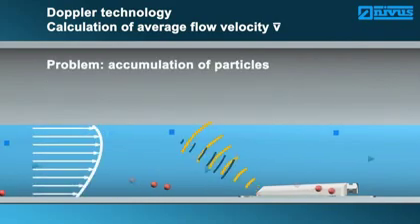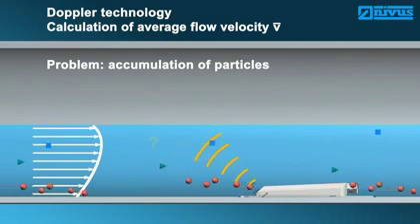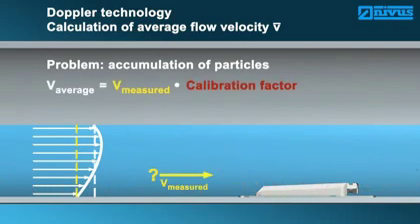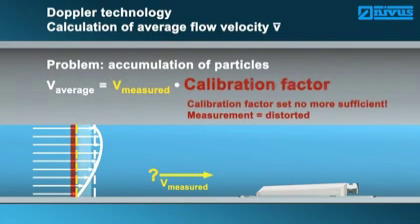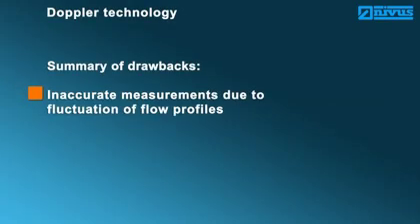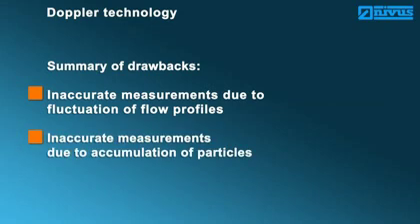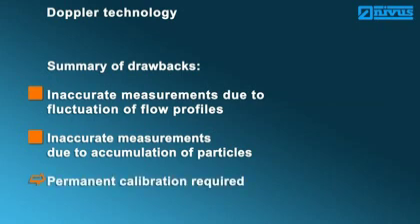Accumulation of particles generates a stronger measurement signal and hence is determined by the sensor as the measurement spot. A local variation therefore creates a distorted reading which varies from the calibration. The shortcomings of Doppler measurement systems as a brief conclusion: faulty results at varying flow profiles, faulty results in case of changing particle concentration, and no permanent calibration possible.